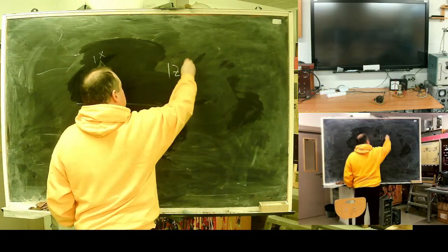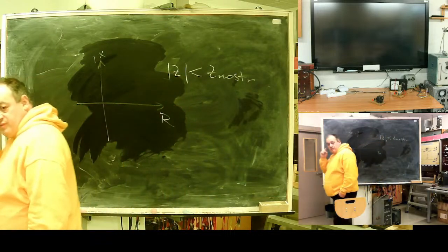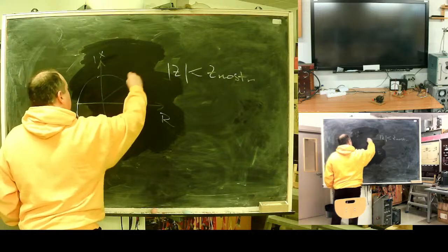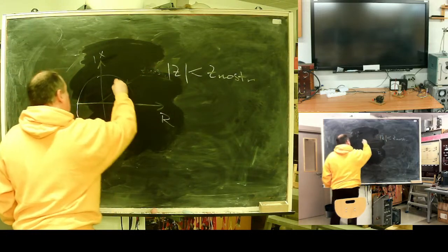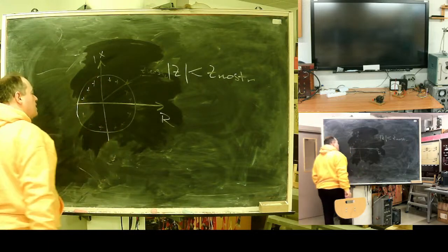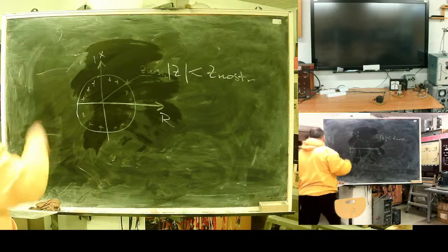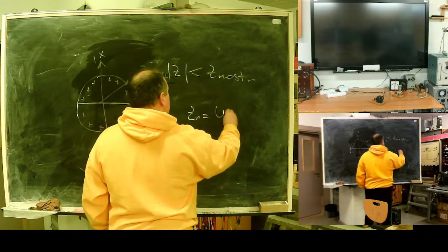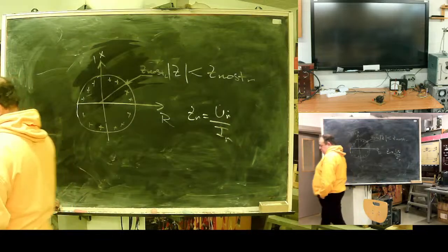If we have a trip condition, what will we see on our complex plane? A circle. Inside the operation area the relay trips, if the observable resistance point is inside this characteristic. So if U relay divided by I relay is inside this area.